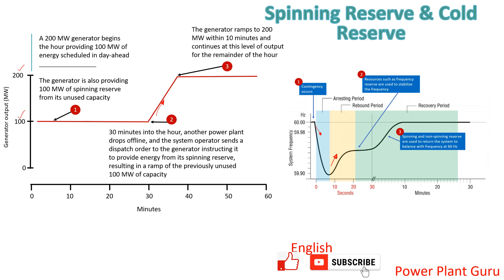The reserve is only said to be available when the machine is running and supplying power into the grid — that means it is already synchronized. You cannot consider a machine which is running on FSNL and having a capacity of 200 megawatt. A machine running on FSNL with 200 megawatt surplus power generation cannot be counted as a spinning reserve because you need to first synchronize to the grid and then that power will be available. That kind of power is called hot reserve. So you can synchronize that machine very fast and pump that power into the grid.